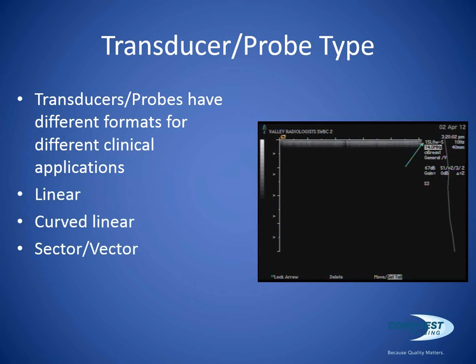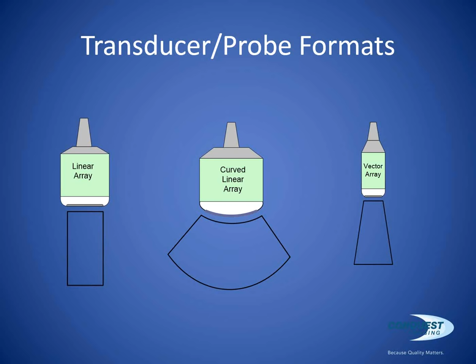If you look at our linear probe, the linear probe is typically used for vascular studies or small parts. And small parts is an exam type that usually refers to various parts of the body that include breasts, testicles, thyroids, and maybe even some musculoskeletal work. So that's what you'd use a linear array for. The curvilinear array is typically used for abdominal work. It is also used on endocavity probes. And then our vector array or sector array, which is the third one, that is typically used for cardiac work, although it's used in some abdomen work. But the problem with the vector array, as you can see from the image format, is that the near field is very small, and the image quality in the near field on vector or sector probes is suboptimal. And so typically curvilinear probes are used for abdominal and obstetrical work.